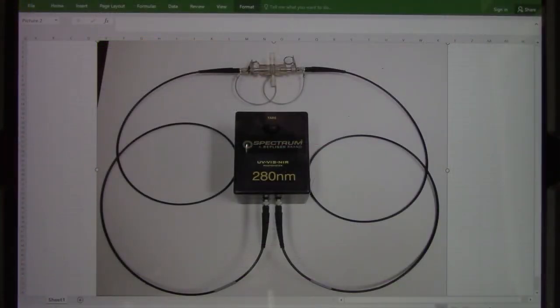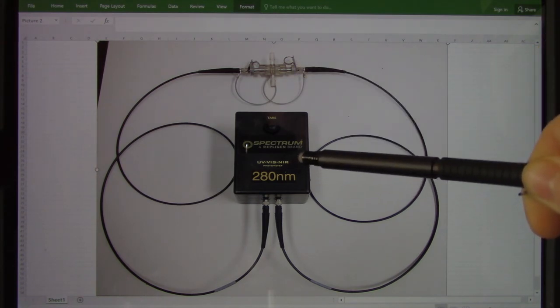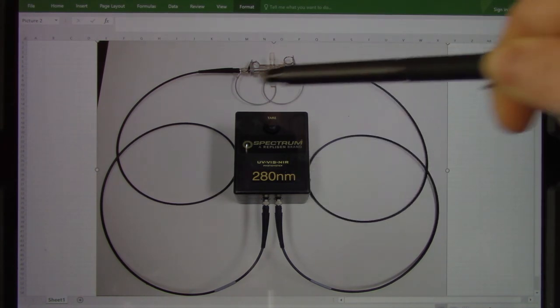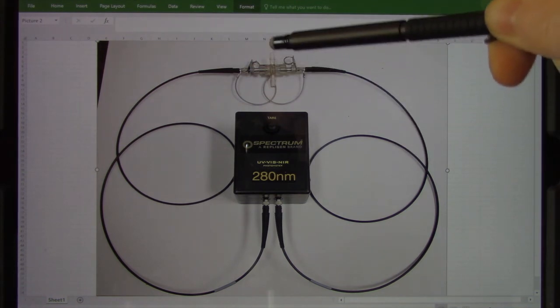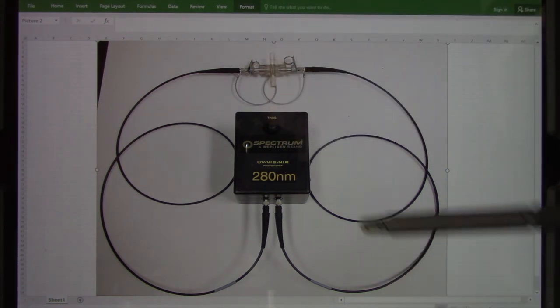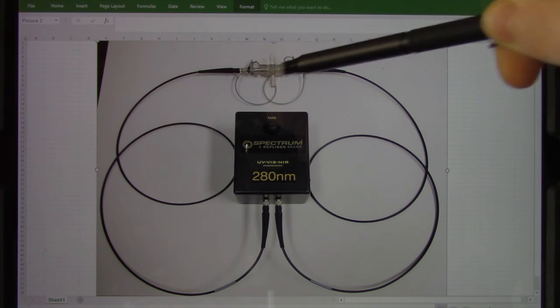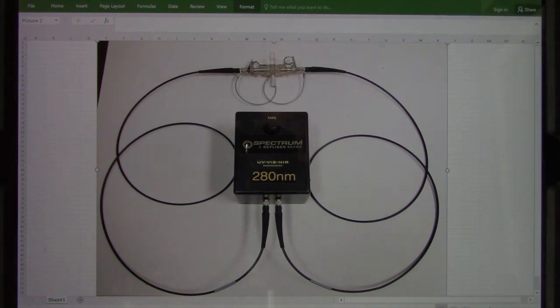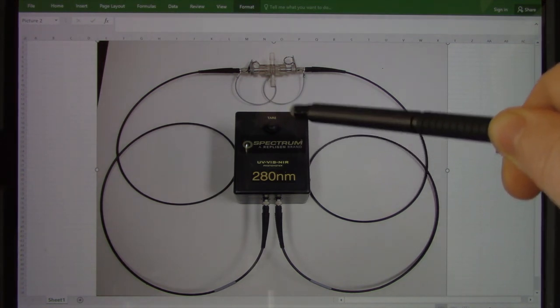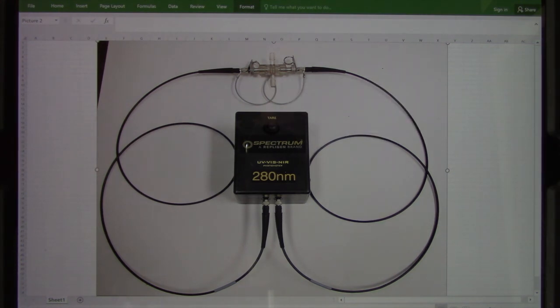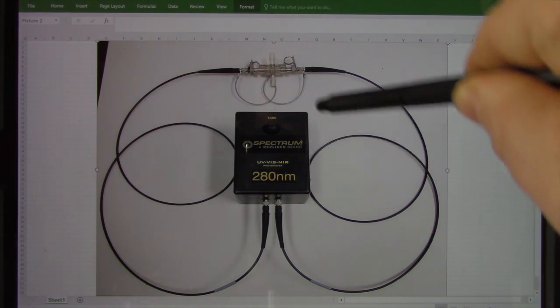For those customers using the optional UV-vis, either A280 or 260 or both, each one has a sensor and each one has a light source. The light source comes into each end of the sensor, and the fluid flows through the sensor. I recommend to customers to wrap these in aluminum foil to avoid any incident radiation from the light affecting the measurement. And you can see here there's a tare button. Only push the tare when it's full of buffer. If you don't, and you tare it with 0, then it's taring with air.